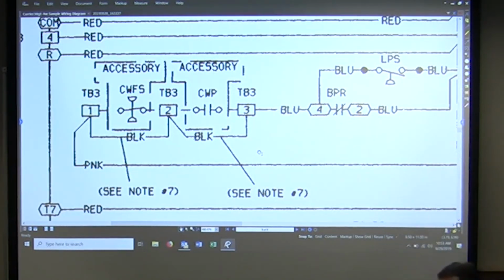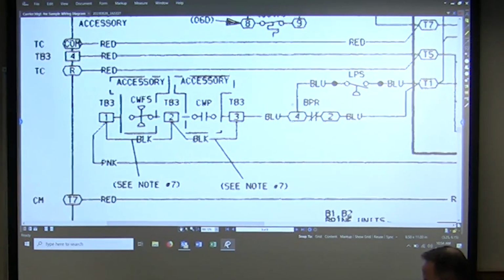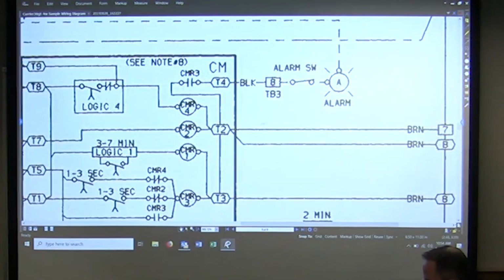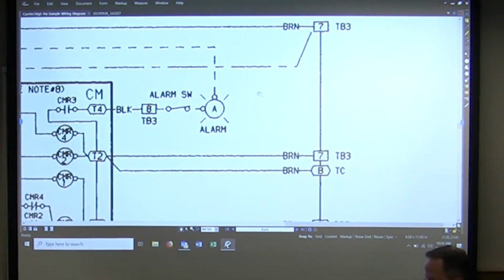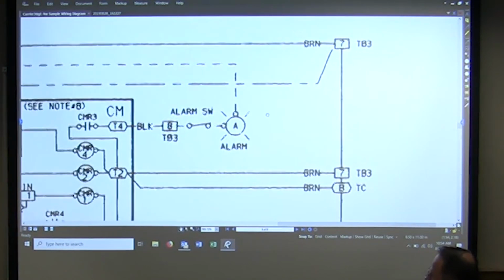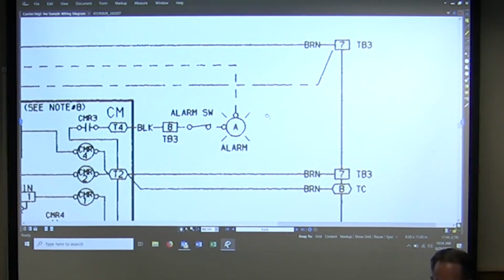3, where would you hook up either a visual or audible alarm? On 3? Yeah, number 3. We skipped 2 because 2 is the same. It's right next to it, the same exact kind of setup. The alarm switch. Yeah, TB3, TB3/8. So right there. We have dashed wires, so that means field installed.